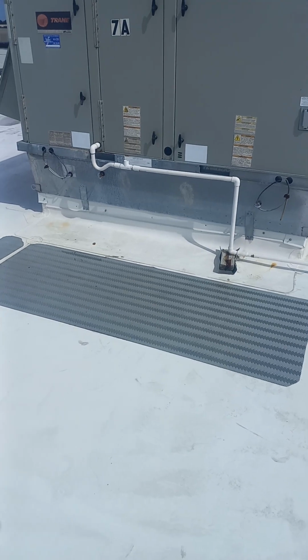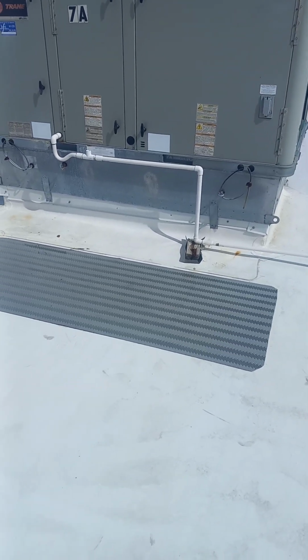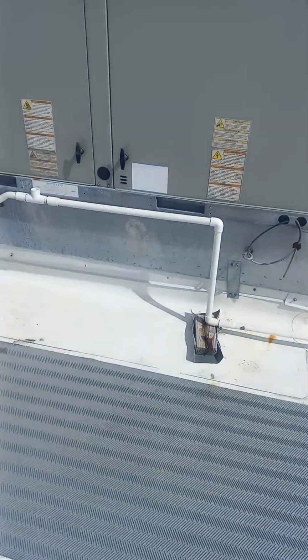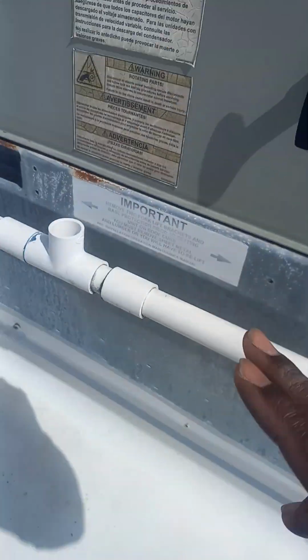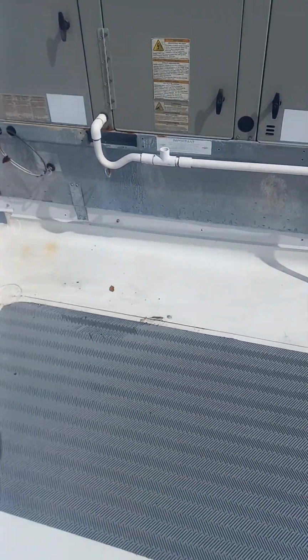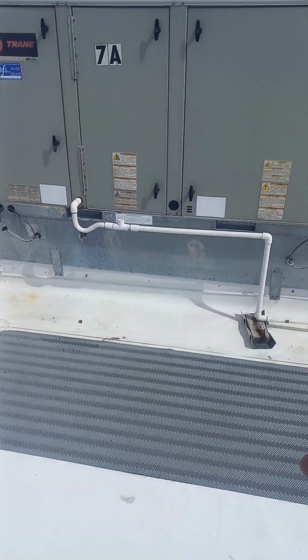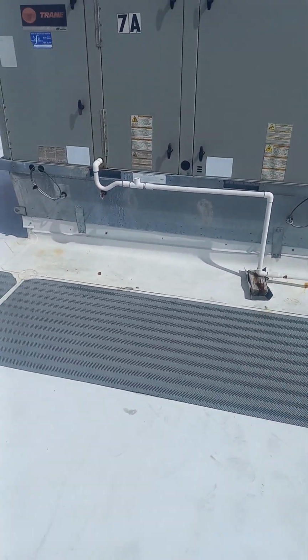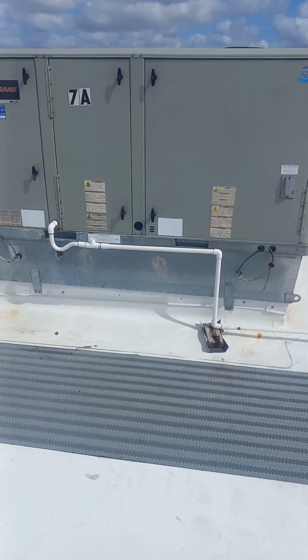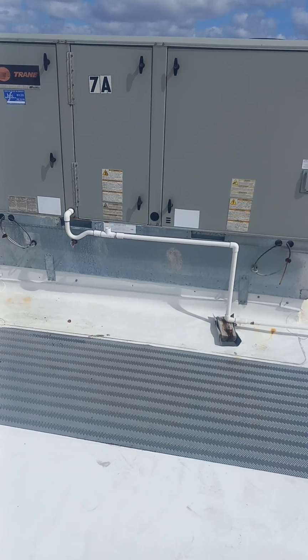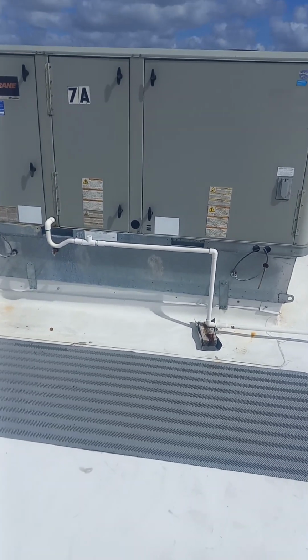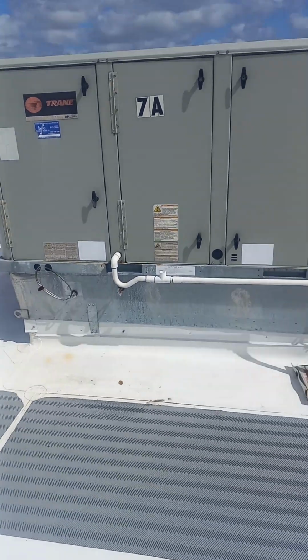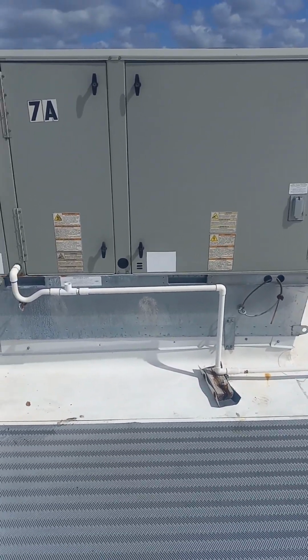So all of these units, they have a standard curb. So this is a flooring, and then this is just like the curb section to sit the curb adapter on. The unit is sitting on the curb adapter. So you have the curb, and then somebody designed the curb adapter with the dimensions of the curb itself, and then get the dimensions of the unit, and they make a sheet metal adapter so the unit can fit on there. And then you have a supply and a return plenum section.